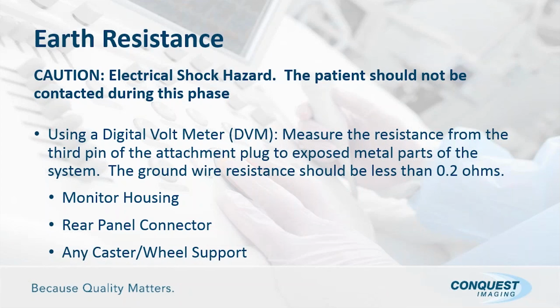And specifically, this requirement of 0.2 was out of a GE manual, and that's because the GE manual specifically says in NFPA standards you have to comply with them. I'd just like to make a note, though. In 2015, this 0.2 ohms was changed by NFPA 99 to 0.5 ohms. So even though now the GE manual says 0.2 ohms, that was based on an old condition of NFPA 99.